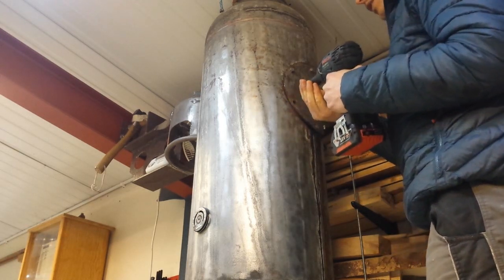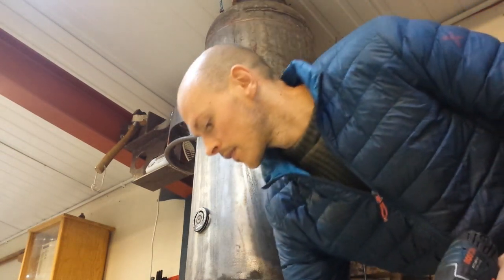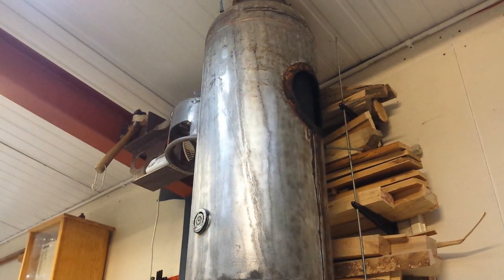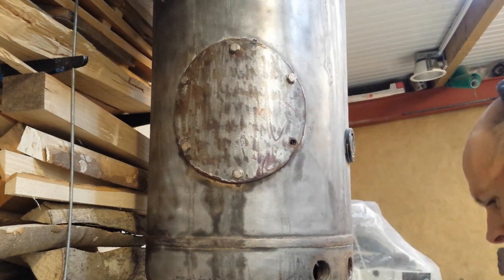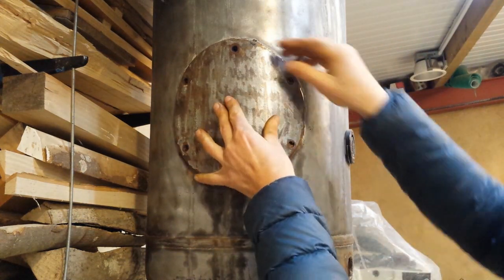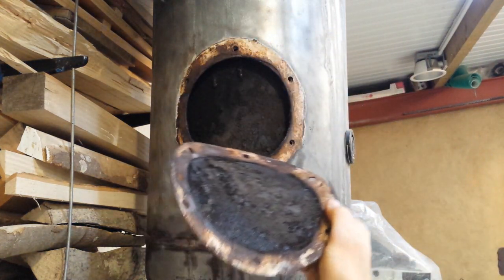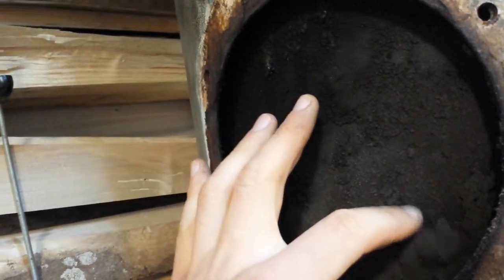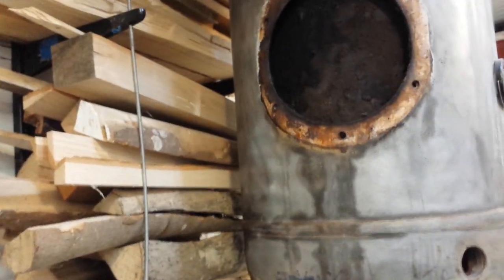Let's get rolling with fixing this anyway — taking off the access panel for the heat exchanger. That battery-powered impact wrench is pretty awesome but vibrates humongously over that steel canister — really loud. It doesn't look awful, that's my initial impression. Trying to see in there and it doesn't actually look too bad. Looking around the other side in the lower hatch, I'm certainly going to need to replace these heat-resistant gaskets. That looks a bit worse to me.